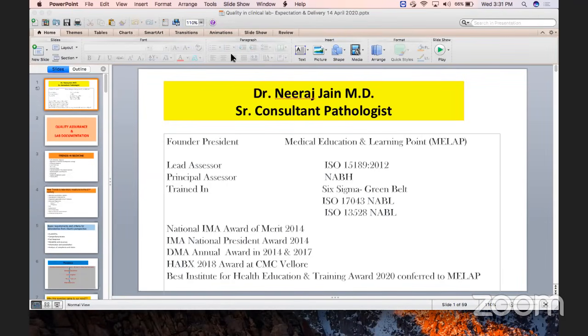Because sometimes what people say, we are following clear guidelines. They are saying 20% variation is possible, 15% variation is acceptable, without realizing what the meaning of 20% is. 20% means, suppose I am saying hemoglobin is 12 today, and tomorrow I will accept 20% variation. That means 20% variation is 2.4. If my hemoglobin is 9.6, I'm accepting that. If my hemoglobin is 14.4, I'm also accepting that. Is that reasonable? You have to develop your acceptability criteria.